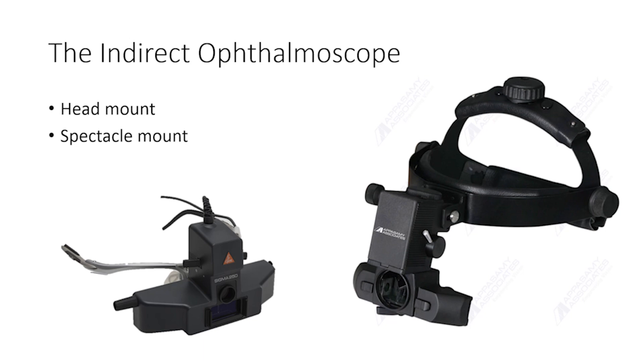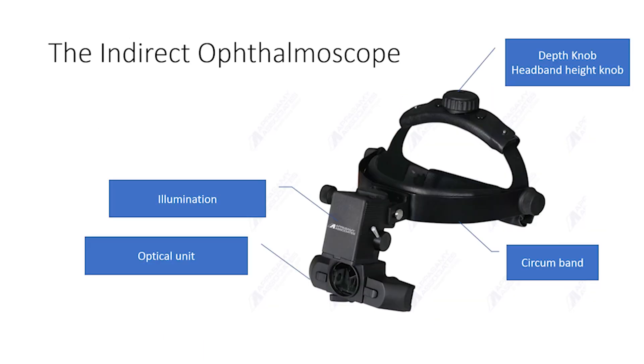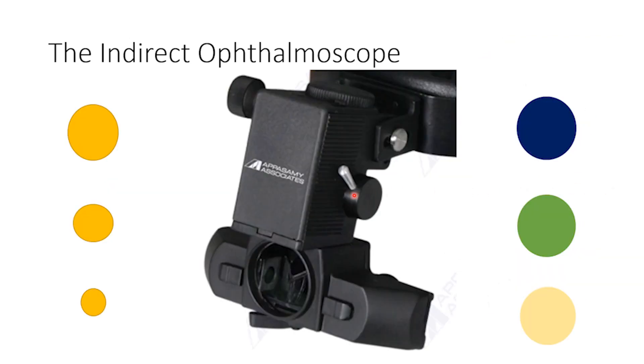There are two commonly available models of binocular indirect ophthalmoscope. The head-mounted model is more sturdy and the more popular one. The spectacle-mount is used for convenience and portability as it can be hung around the examiner's neck when not in use. The instrument has an illumination source, observation optics, a housing with power supply and electronics, and a headband. The knobs or levers on the sides are for changing the illumination spot size and for using filters like cobalt blue for fluorescein angioscopy, green for red-free examination to look for nerve fiber layer defects, and the yellow filter for light-sensitive eyes.